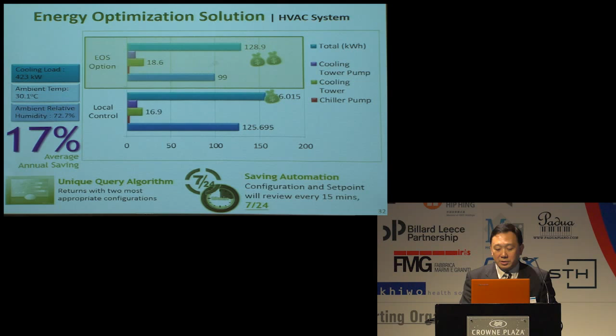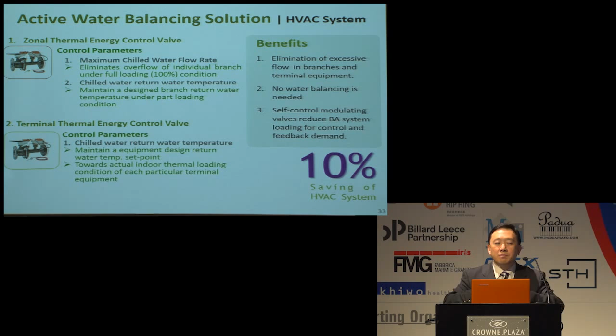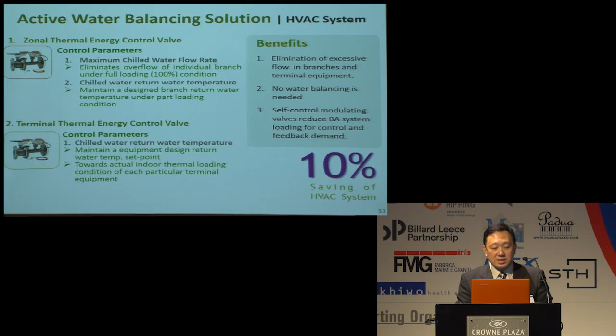Another mechanism we produced is what we call a modulating valve. Basically, it's controlling the chilled water into the buildings. Now, very often in a lot of buildings, I'm sure you experience that one corner is too hot, another corner is too warm. Now, this modulating valve will modulate that to make sure the entire water balancing is correct, and you will not allow any excess flow of chilled water into the floor. So basically, it's giving you better thermal comfort, and at the same time, reduces the amount of energy that needs to be used. And we estimate that they will save another 10% of the HVAC system.